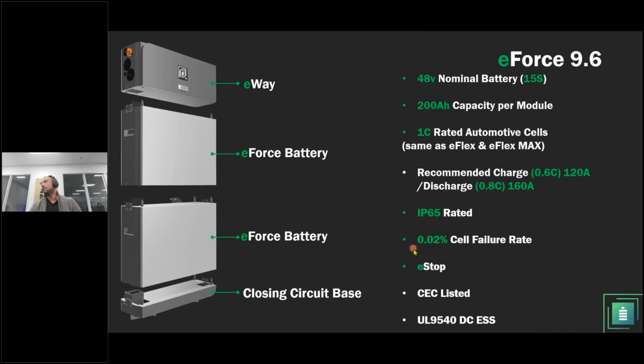It is UL 9540 DC ESS, which, according to the third edition of UL 9540, allows me to certify the system, just the battery itself, as an ESS without the inverter. We can have another session going over UL 9540 that explains the new definitions of ESS, and that it accepts AC ESS or DC ESS.